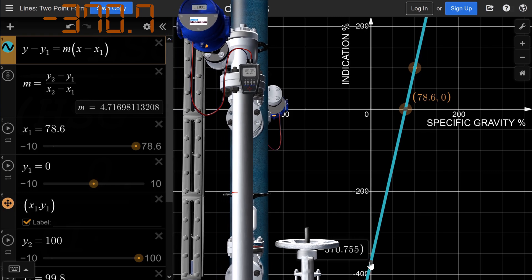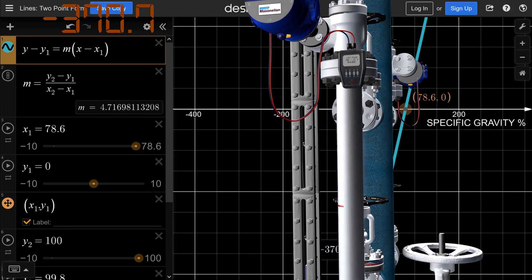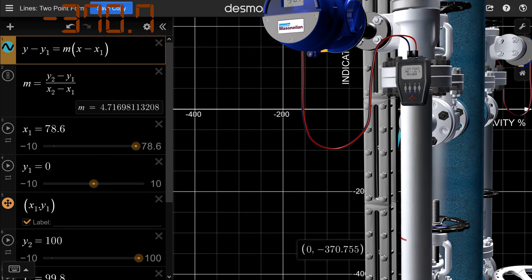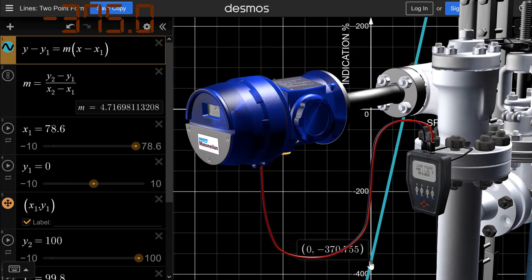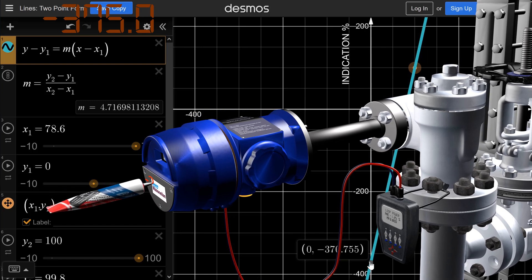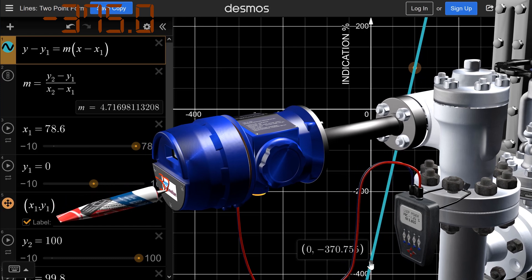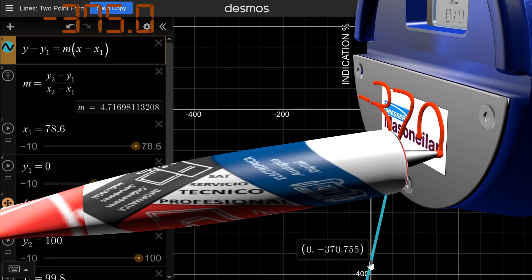The display alters its value around minus 370.7%, which is the correct number for the specific calibration. The intersection point on the y-axis is also minus 370.7. After we found out the value that should be indicated with the Desmos graphing calculator, we compare with the displayed indication. The transmitter responds properly.